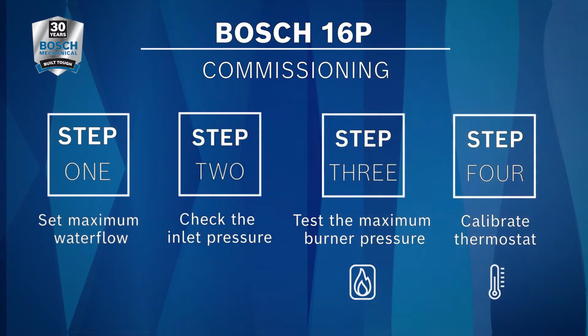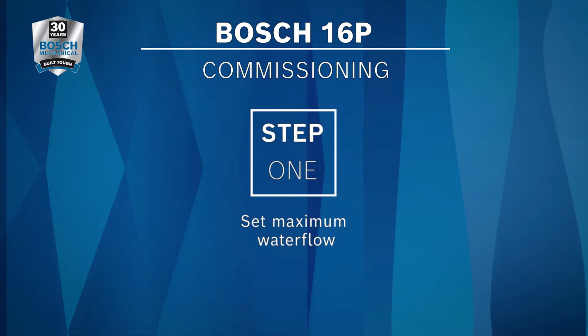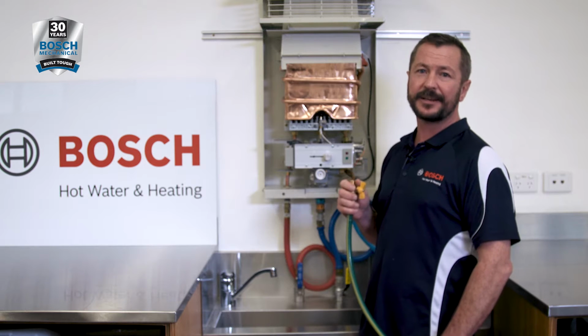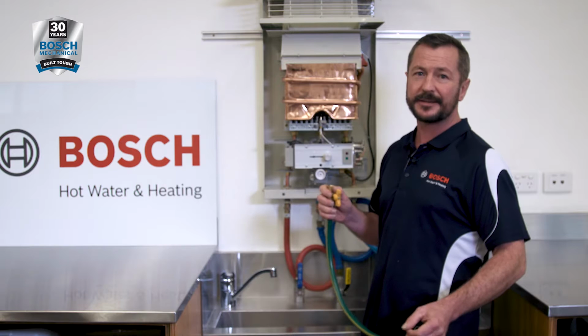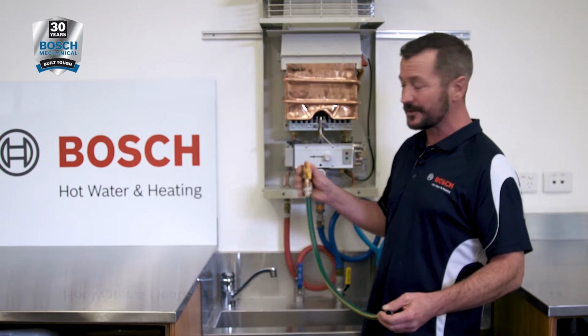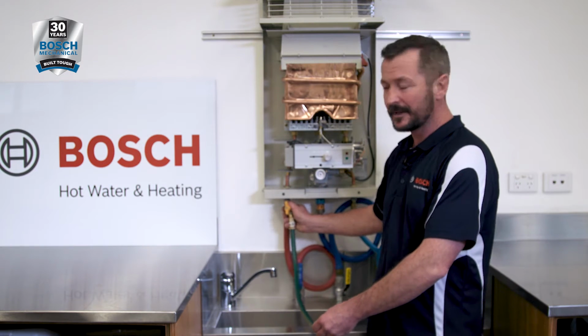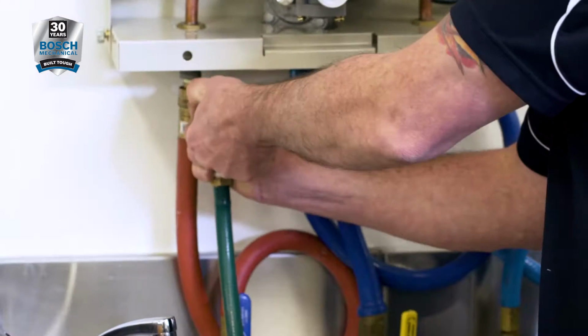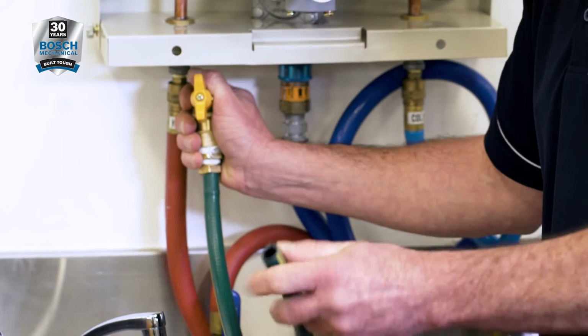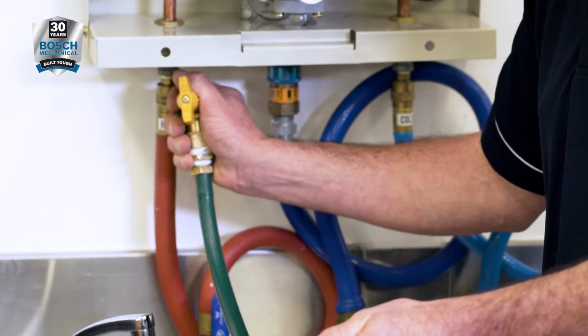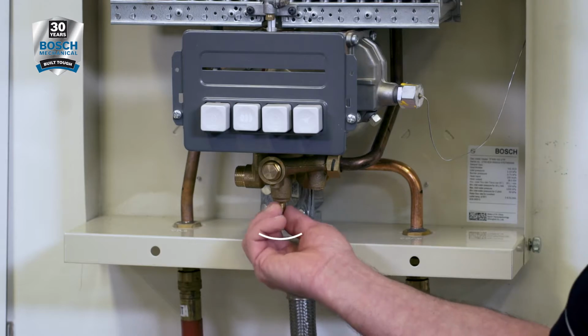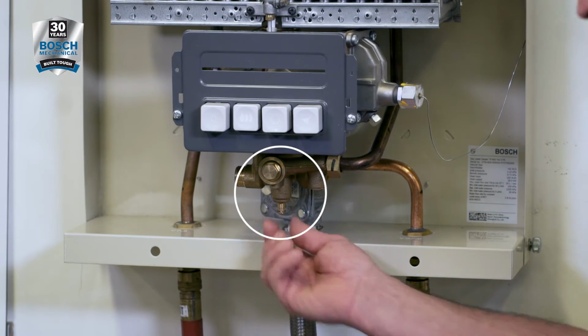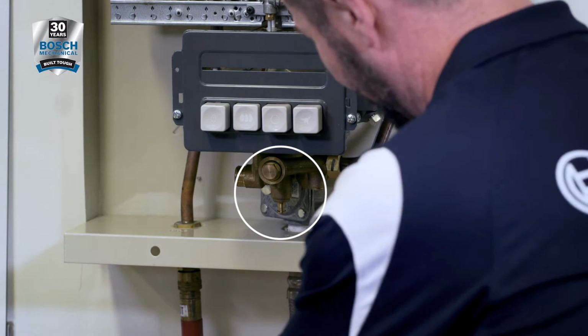First step is to set the maximum flow rate of the appliance of 16 litres per minute. A handy hint for setting flow rates and testing temperatures is to fit a ball valve on a hose directly to the outlet of the water heater. Here you can adjust the flow rate via the ball valve and test the temperature straight out of the hose at the end. Using your flow cup and the adjustment screw at the base of the water valve, open a hot tap.